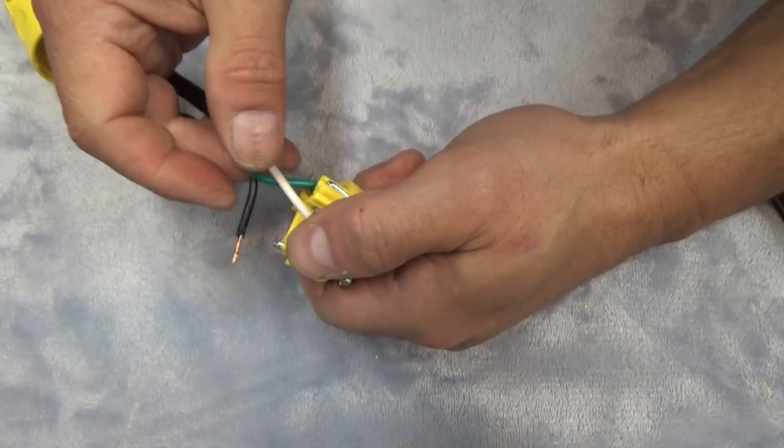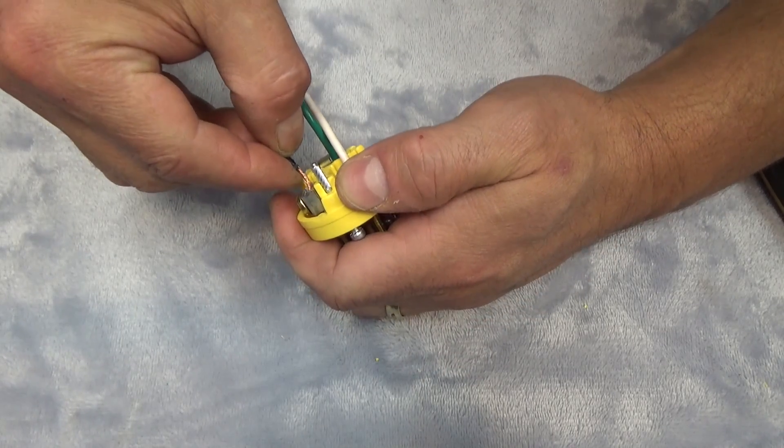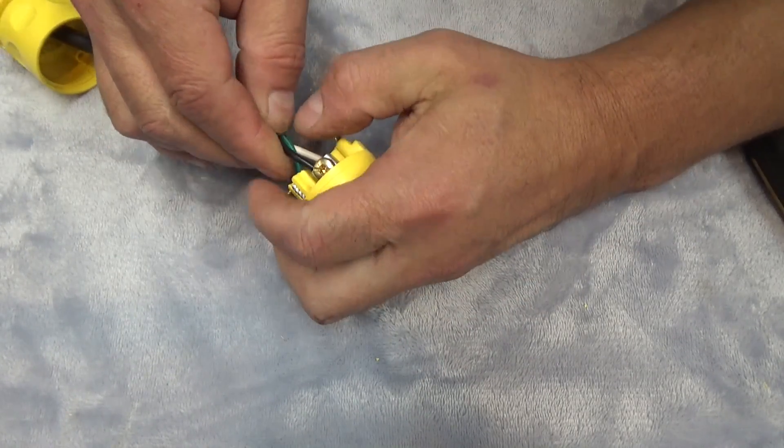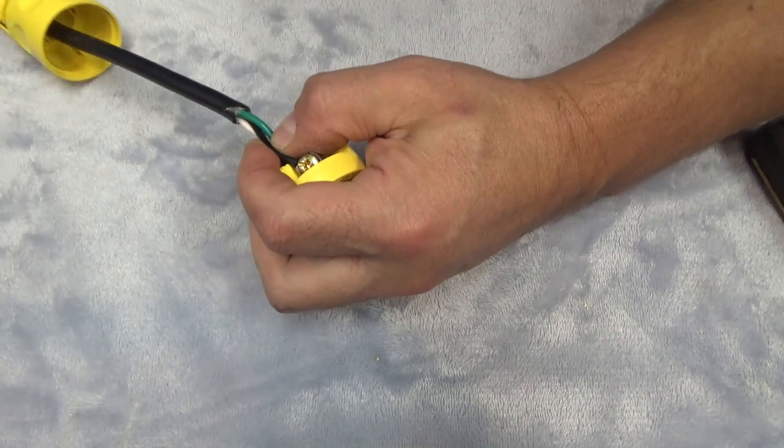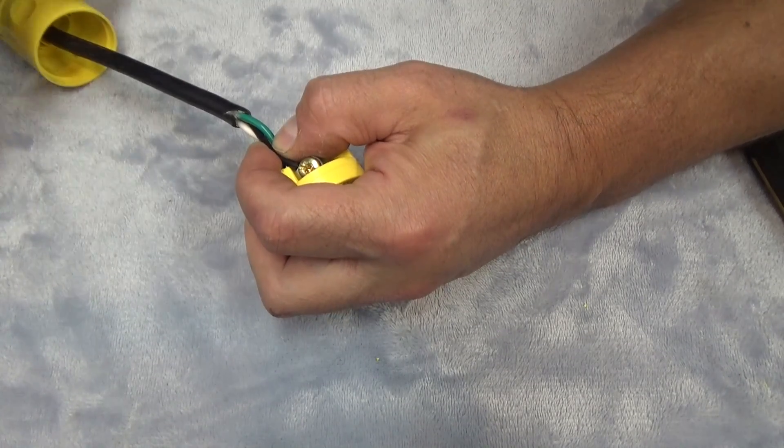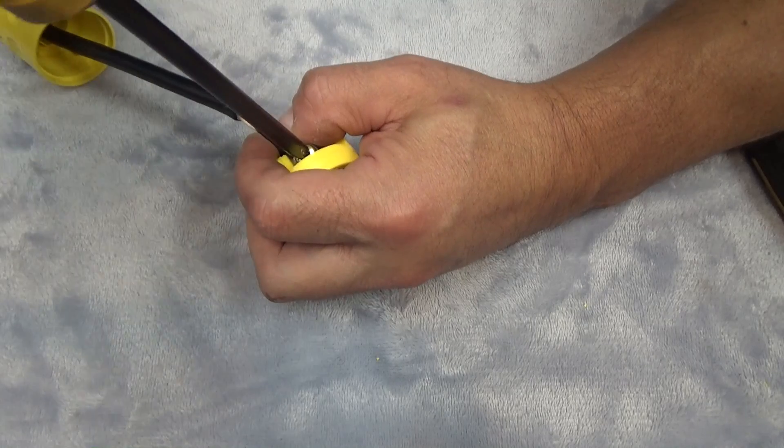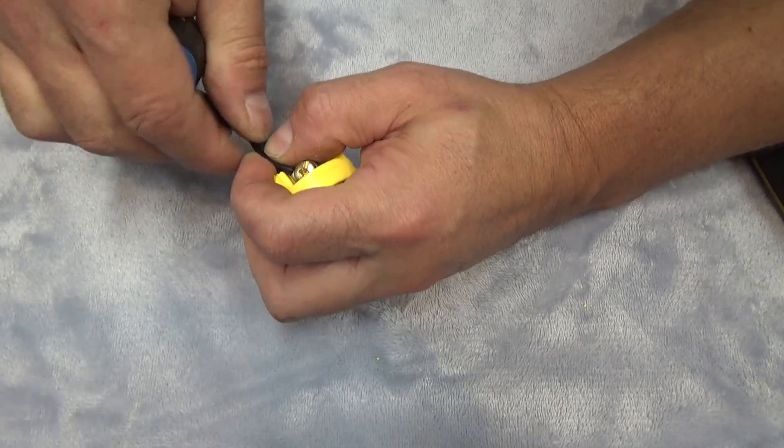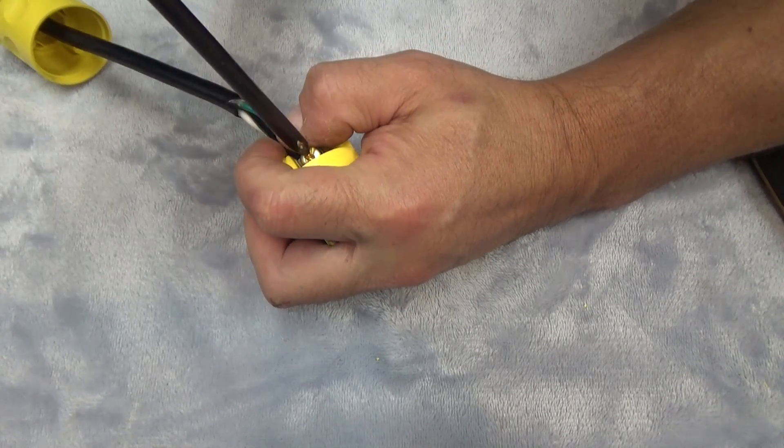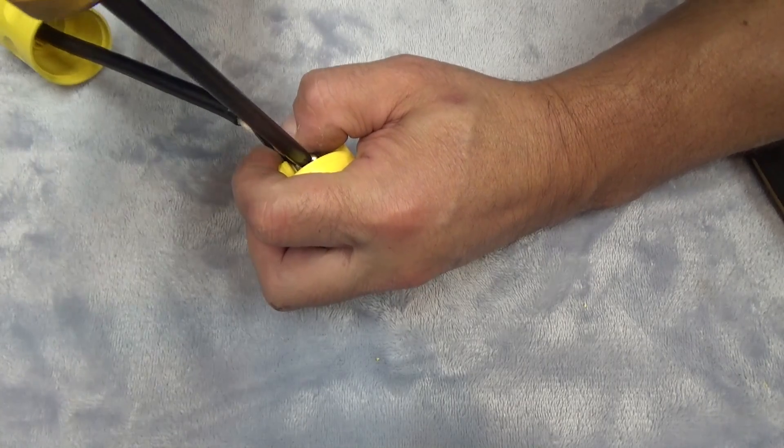This incidentally is a 15 amp, 120 volt plug. If we were doing a 20 amp, it would have a T spade or a spade that's twisted sideways. Let me just get that in just a little bit more here. So hopefully this video's been helpful.